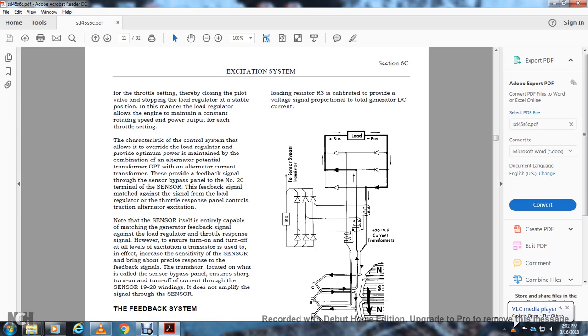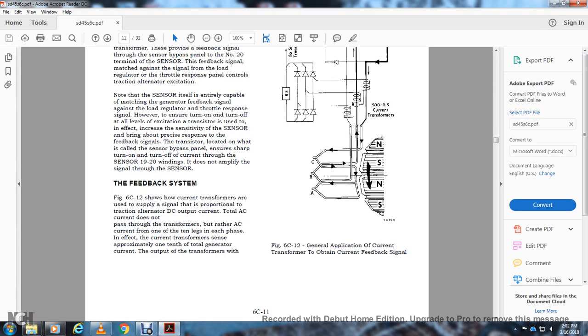The control system is provided with a feature that allows it to override the load regulator to maintain optimum power, with the combination of alternator potential and alternator current provided with the feedback of the signal with the sensor bypass panel, with the number 20 terminal of the sensor. The feedback signal will be matched against the signal from the load regulator throttle response panel, which controls traction alternator excitation. Note that the sensor itself is entirely capable of matching the generator feedback signal with the load regulator throttle response signal. However, the turn on, turn off and all levels of excitation of the transistor ensure an increase in the sensitivity of the sensor, bringing about a precise response to the feedback signal, with the transistor located on the sensor bypass panel. It ensures a sharp turn on and turn off going through the sensor 19 and 20 windings, and it does not amplify the signal through the sensor. The feedback system.